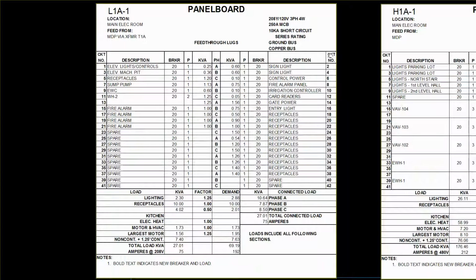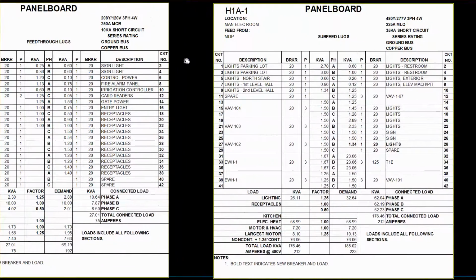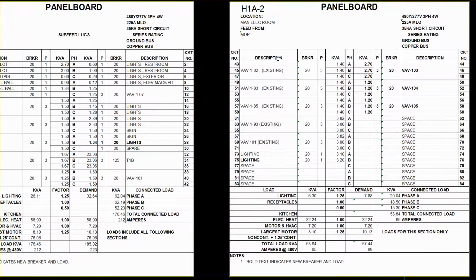And so you'll either see fully rated or series rated there, and it would have been good for us to have had fully rated on there, but here's a 35K short circuit series rating. This is a 480 volt panel. Well, on 480 volt panels, the minimum short circuit rating that you'll find is 14K for individual branch circuit breakers. So what we're saying is that if these breakers, these 20 amp 3 poles and 20 amp single poles that you see here, are put in series with another breaker, and the manufacturer has tested them to work at 35K with the cheaper breakers and maybe one larger expensive breaker in the MDP, then there's a cost savings to be had there. Now there is an exception within the code that keeps you from doing series ratings, but we won't go into that here.